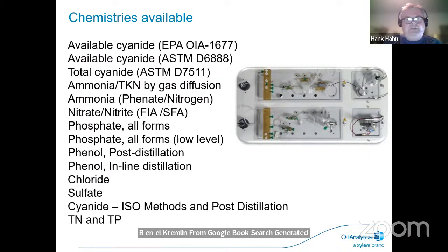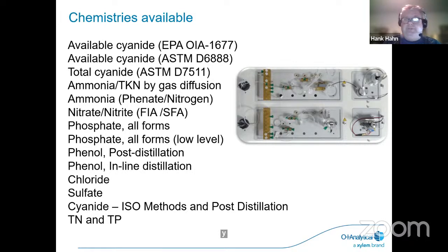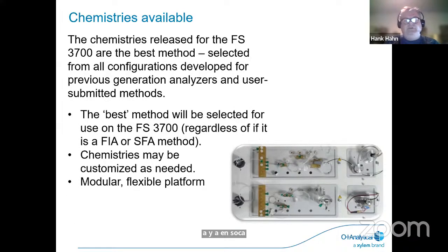We have quite a bit of chemistries available for this instrument. We've got all the different cyanides. You've got ammonia TKN by gas diffusion, which allows you to eliminate the distillation step as well. We have ammonia phenate nitrogen, your nitrate nitrites by flow injection or segmented flow, phosphates in all forms, phosphates low level. We have phenols, chlorides, sulfate. We also do the cyanide ISO methods and post-distillation method. We've got total nitrogen and total phosphorus, also working on some other chemistries as well, sulfide and silica. So the chemistries available that we've released were made to a best method and selected from the configurations developed with the previous generation of instruments.